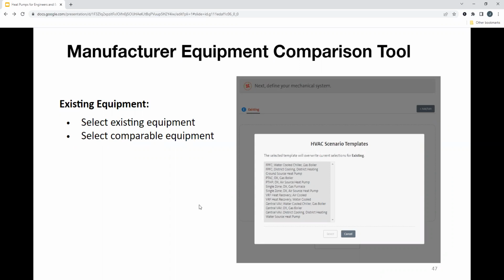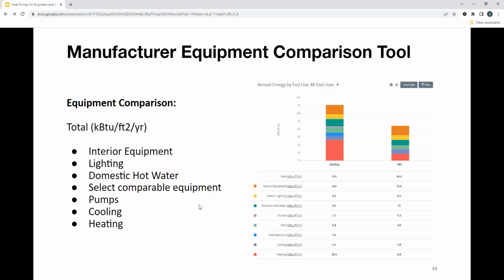And basically, we get this right here, which is an equipment comparison report. There's a bunch more information. I just wanted to show you 2 slides on this, but the kBTU per square foot per year, and it shows you all these interior equipment, lighting, domestic hot water, pumps, cooling, heating, and shows you what the existing system looks like versus if you install VRF with the same utility rates. This is what you might be looking at for operational cost savings.